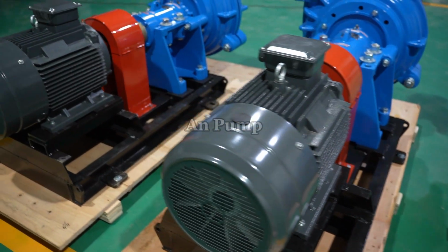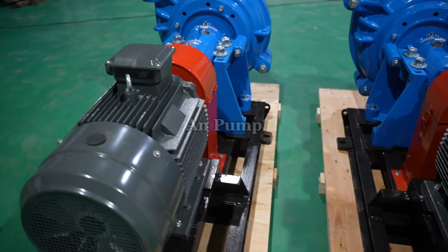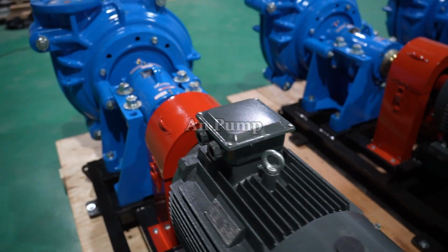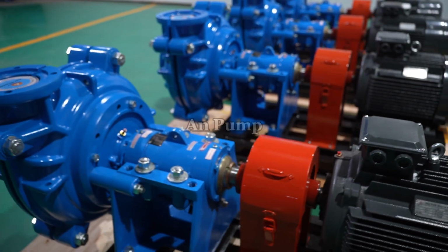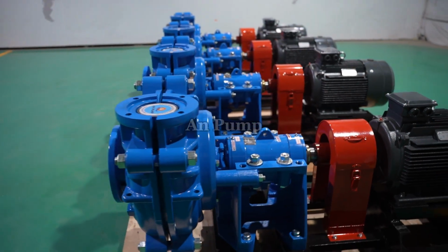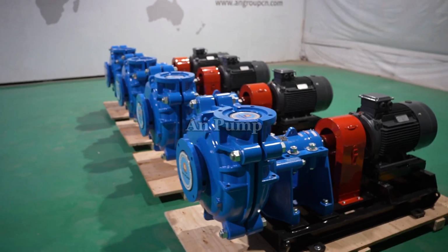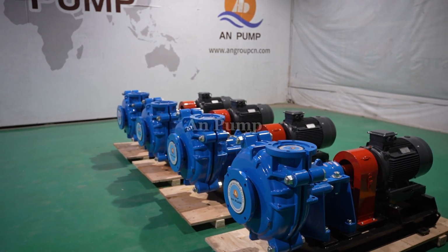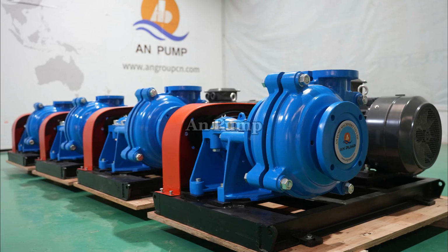The most critical design decision is the material selection for the wetted end. High chrome white iron gives excellent abrasion resistance for sharp, fine to medium particles. Natural rubber or polyurethane liners are better for rounded particles and corrosive slurries. And for acidic or alkaline slurries, you might need duplex stainless steel or Hastelloy. The impellers are usually semi-open or recessed vortex designs with wide, thick vanes and generous clearances. This lets oversized particles pass without jamming.